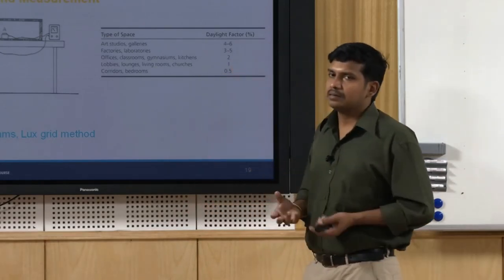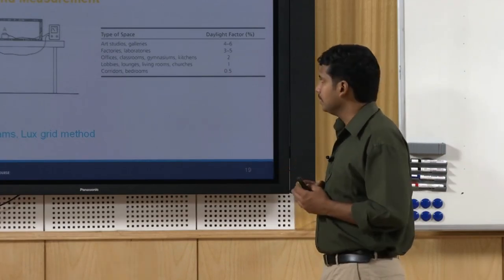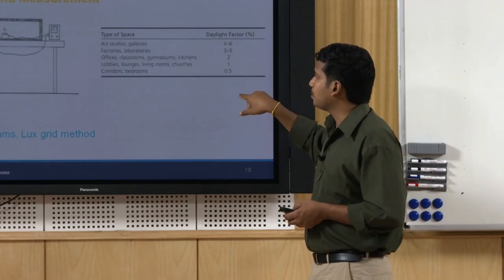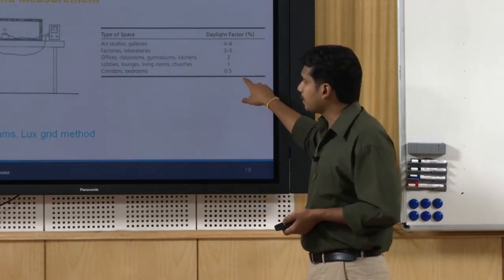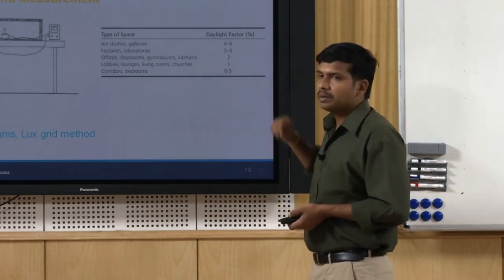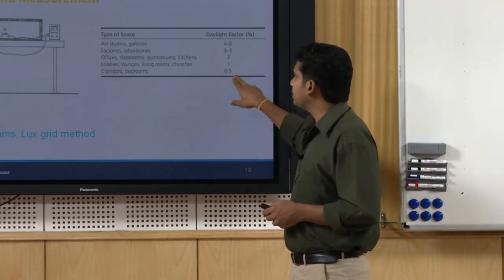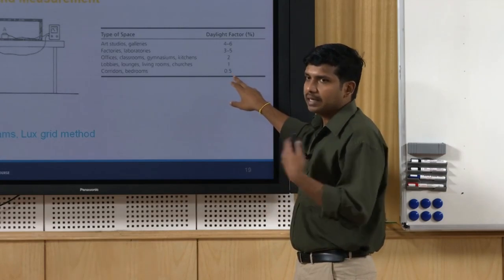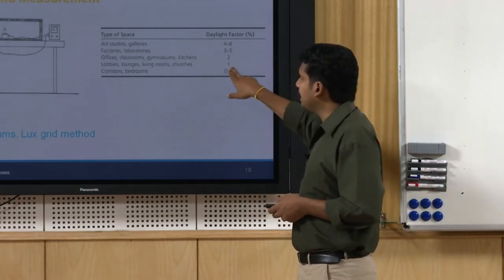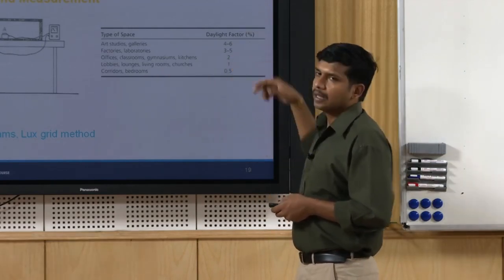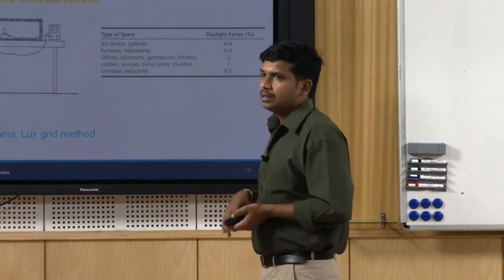Standards also specify daylight factors by space type. For example, corridors may need 0.5% daylight factor and lobbies/lounges 1%, while laboratories may need higher values. In India, with 8,000 lux design sky illuminance, 0.5% equals 40 lux, 1% equals 80 lux, and a higher factor like 5% equals 400 lux — that is what these specifications translate to in practice.